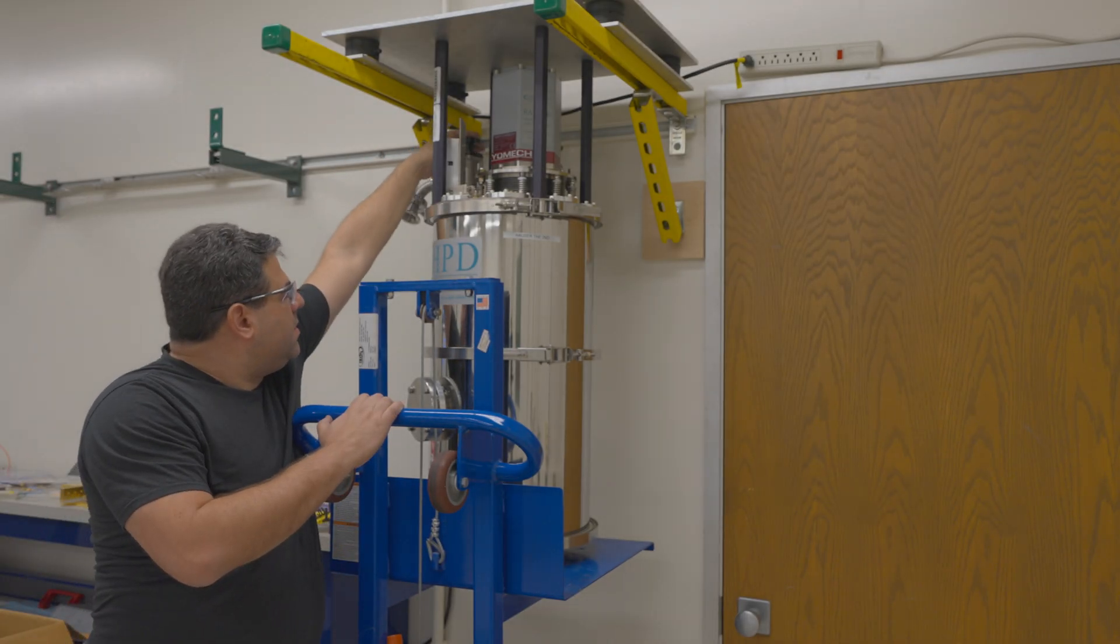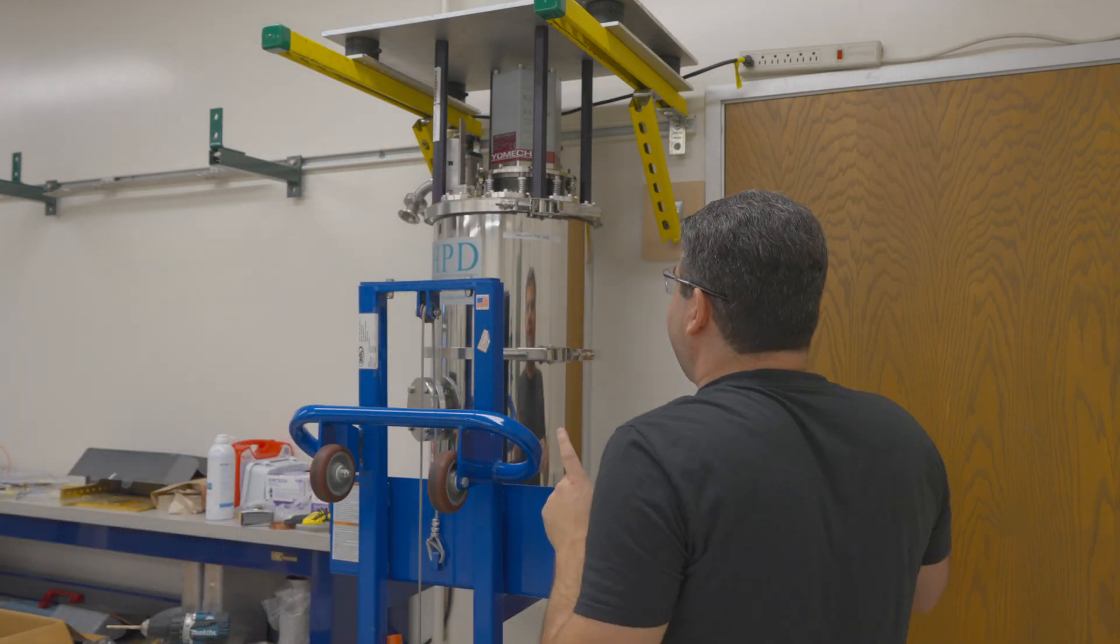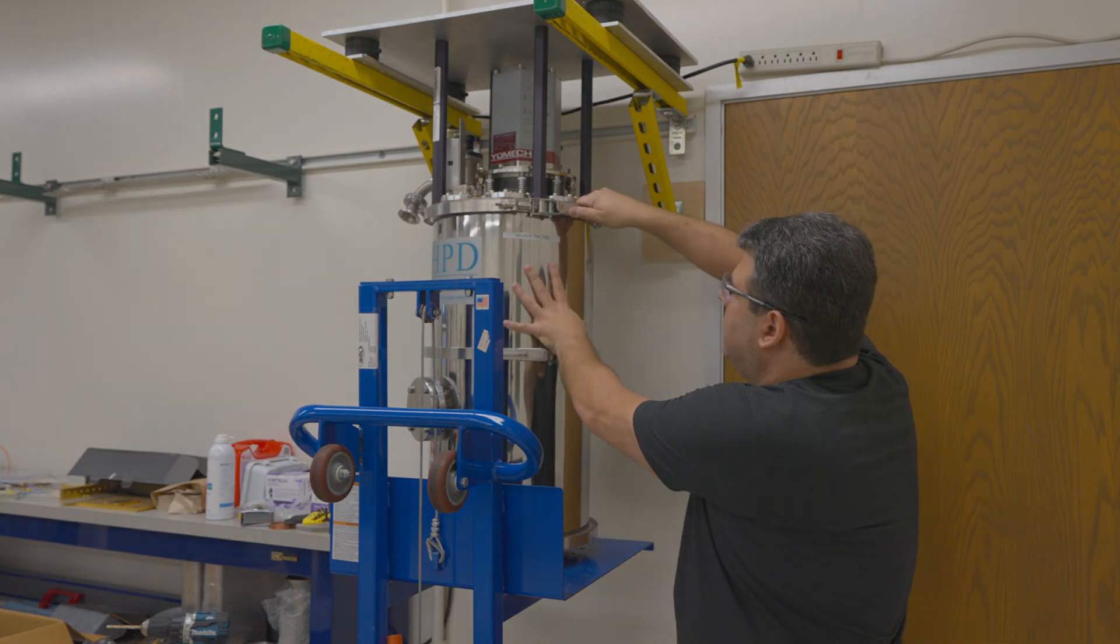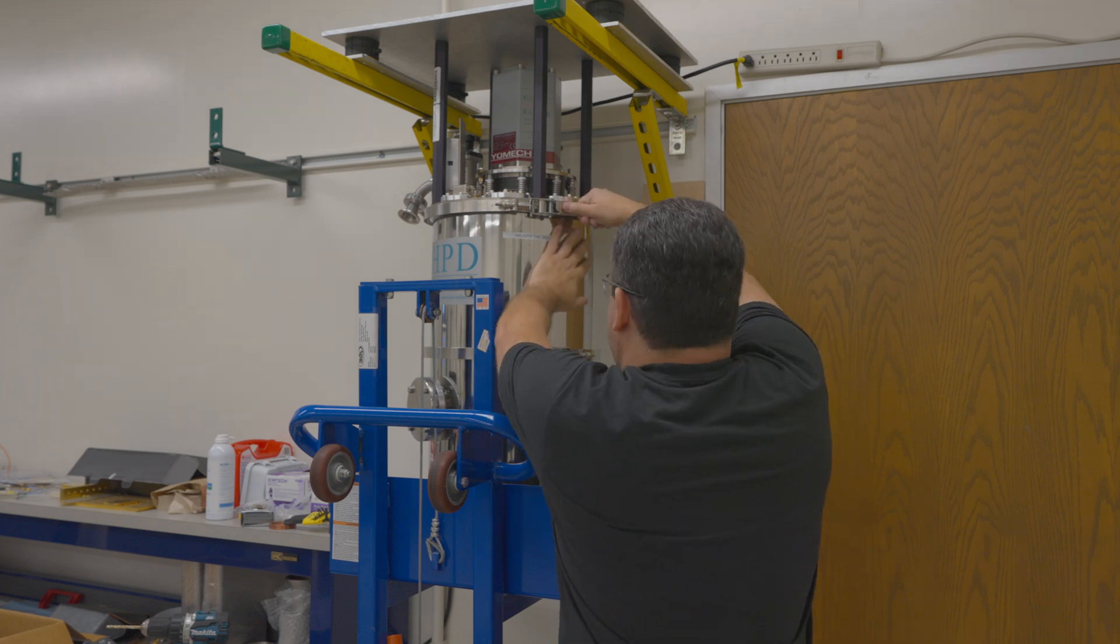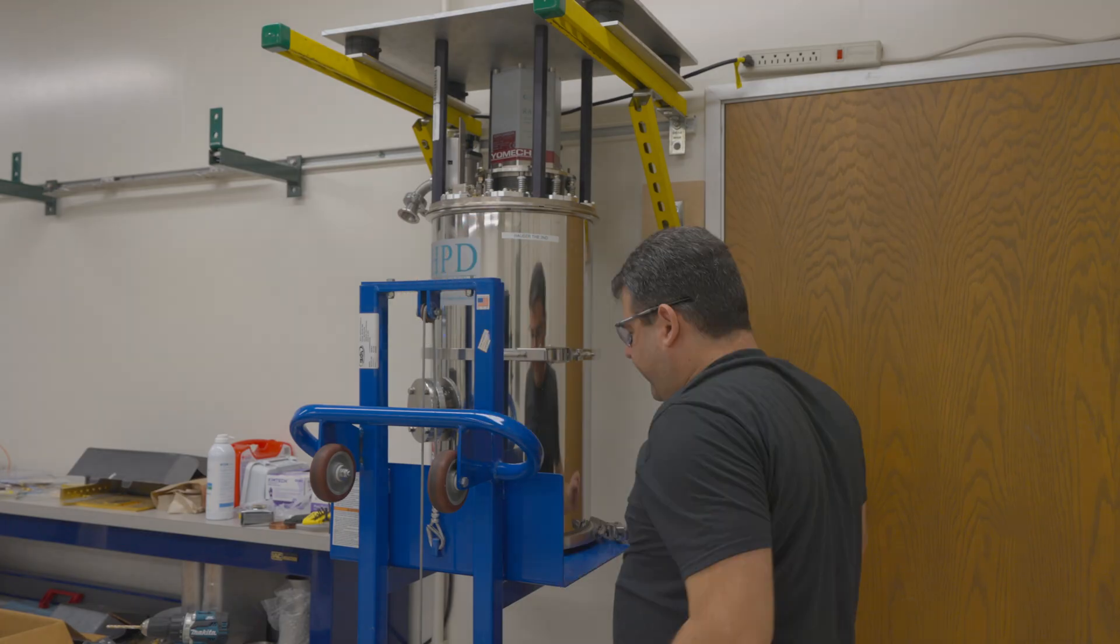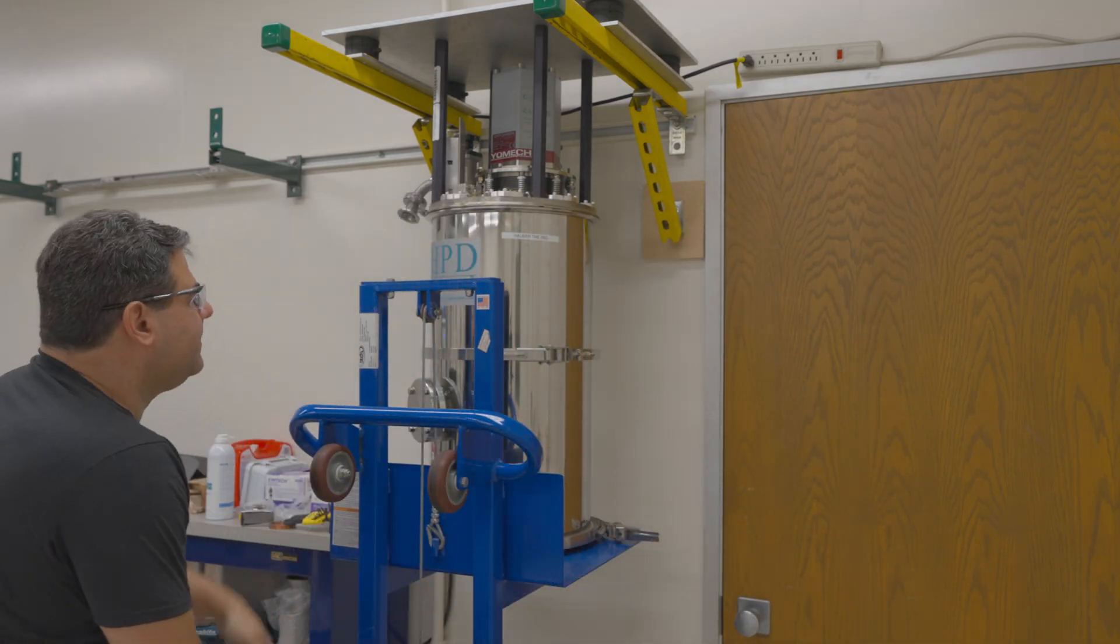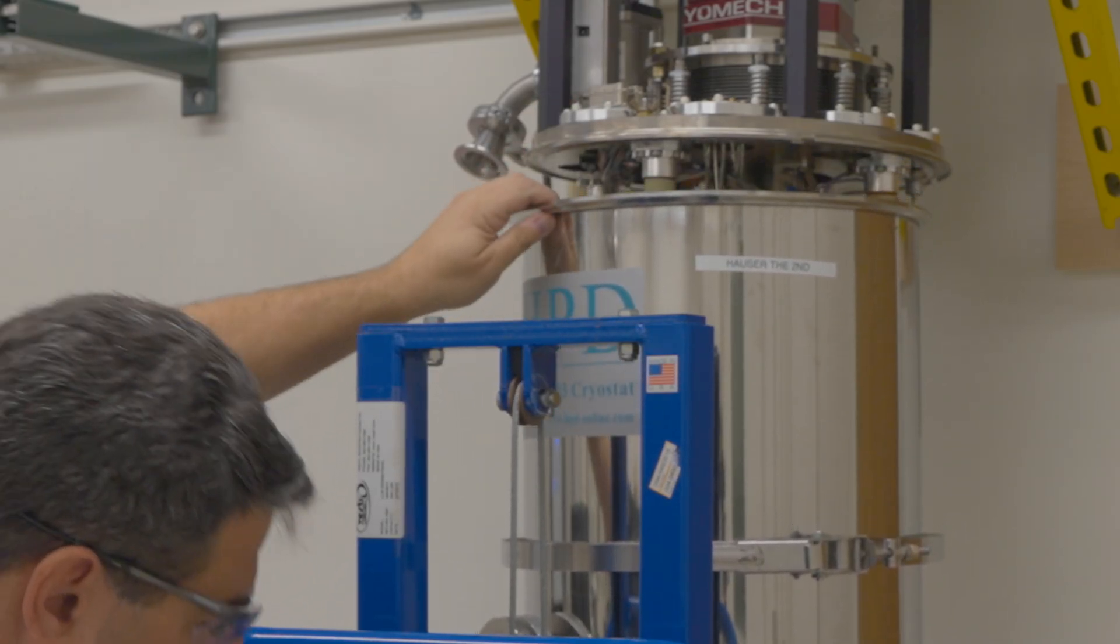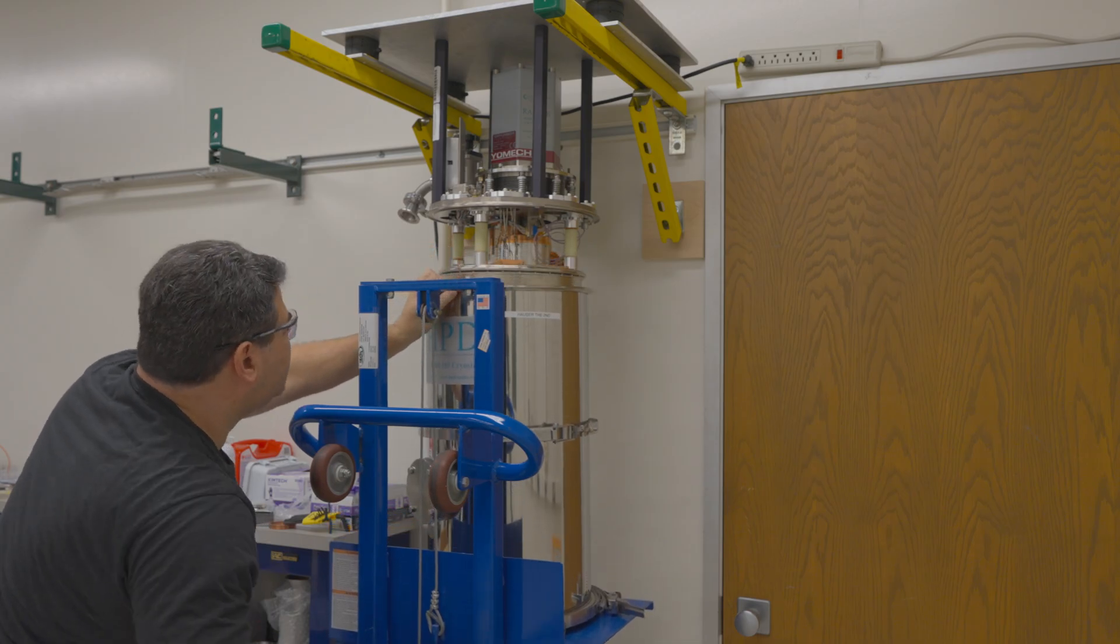So vacuum's broken. Now we can remove the shields. These fridges have a really nice system. So instead of having to take off a million bolts, we can just open up these clamps, I think. Never done it before, so we'll find out. Oh yeah. So now we should just be able to lower the shields off of it.